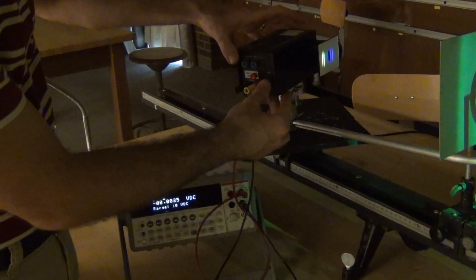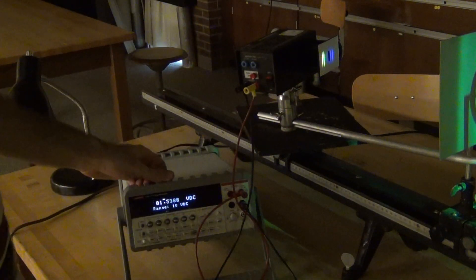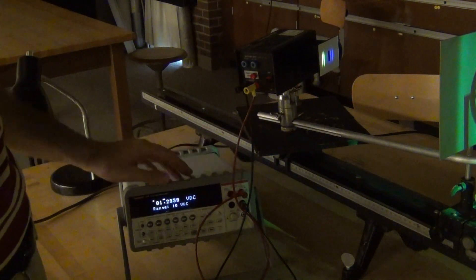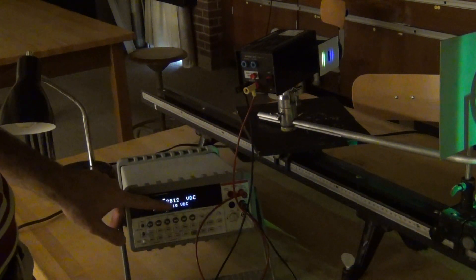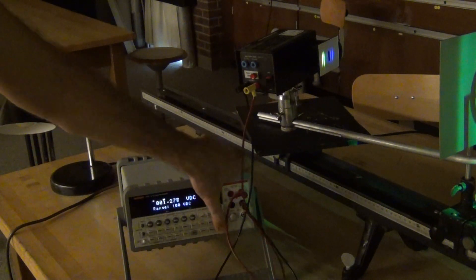To make a measurement, make sure your photodiode is turned on. Have the output of the photodiode connected to the input of a multimeter that's on the 10 volt range. You can adjust the range if needed with these arrows.